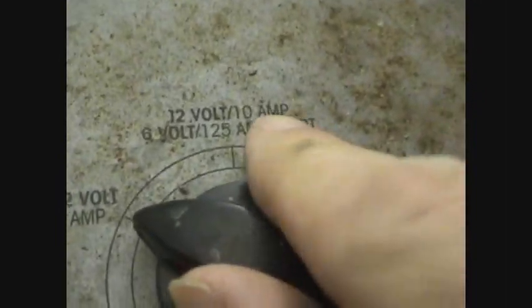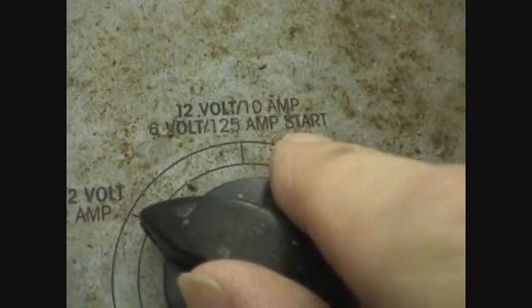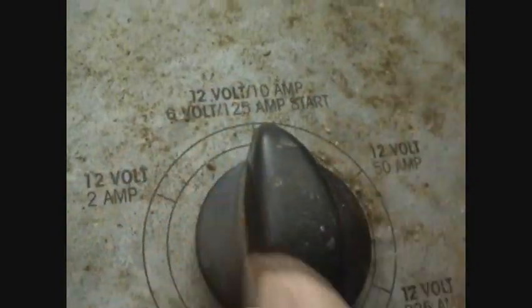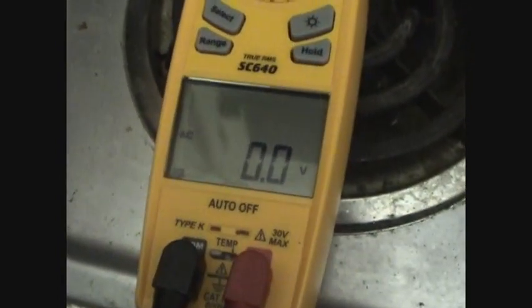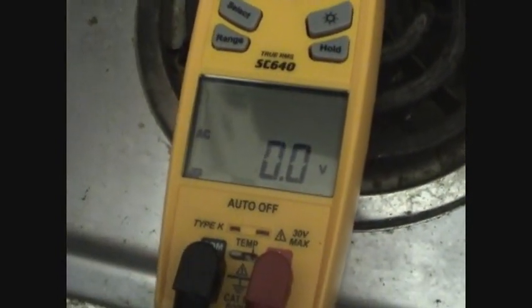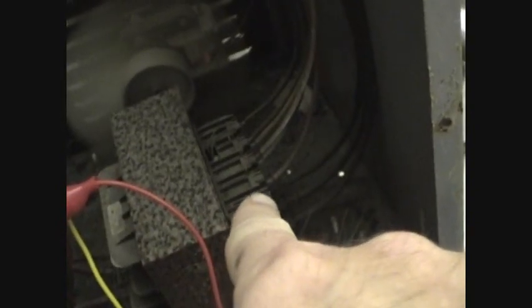And we'll go to this one here, 12 volt 10 amp or 6 volt 125 amp start. And it looks like we don't have anything. I'll have to troubleshoot that further - either the switch is bad and not applying power to the appropriate leads on the transformer, or that particular tap on the transformer is bad. I didn't catch it on the continuity test.